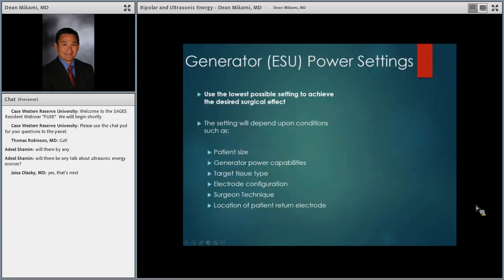So once again, the key message here, and what we want to try to repeat over and over, is to use the lowest power setting to achieve the desired surgical effect. A lot of times we're talking about using cut. Actually, in laparoscopic cholecystectomy, you should never use coag. You should use the cut waveform to do your lap choles. But if you survey 1,000 surgeons, I bet you 995 surgeons say they always use coag. I know in my training, our attendings would say turn off the cut mode when you're doing a laparoscopic cholecystectomy, but the answer is you should use the cut mode. Once again, you can use that continuous cut mode waveform or a blend form to achieve your surgical effect.